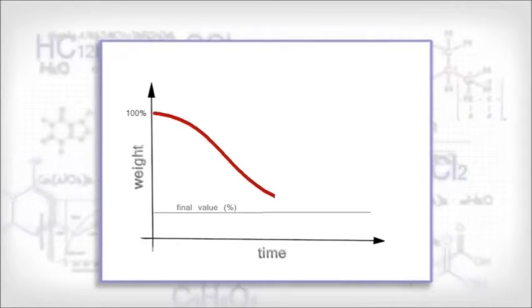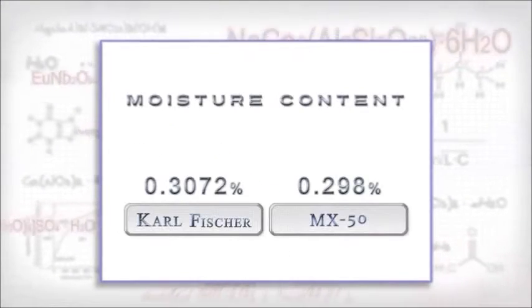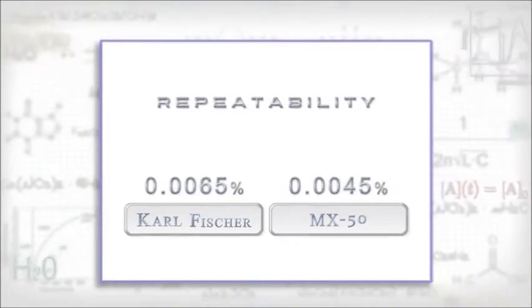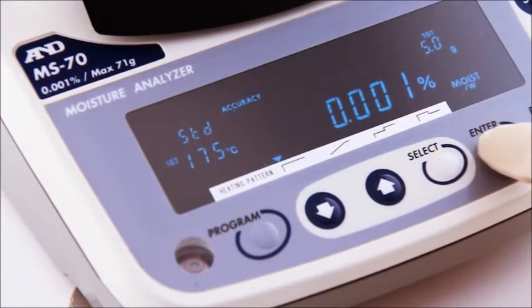A&D analyzers use the thermogravimetric, or loss-on-drying, principle and offer the accuracy of the Karl Fischer technique, but in less time and with better repeatability. Use the preset functions or take full manual control of your measurements.